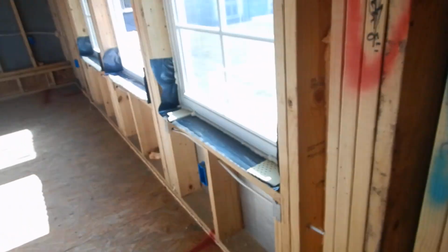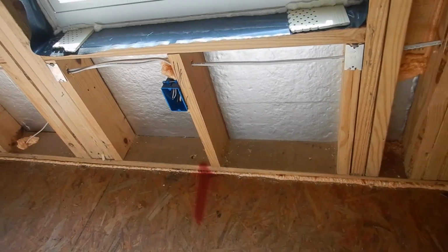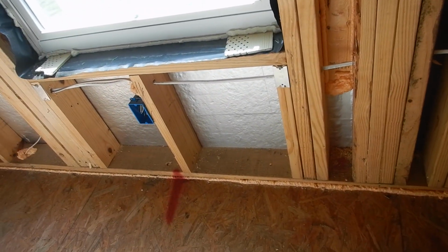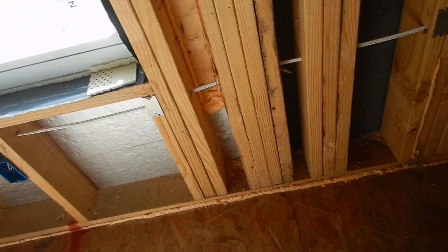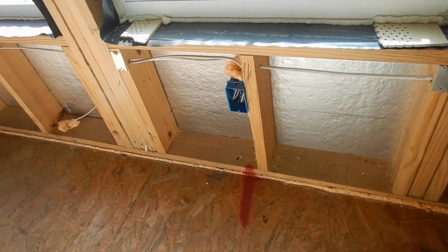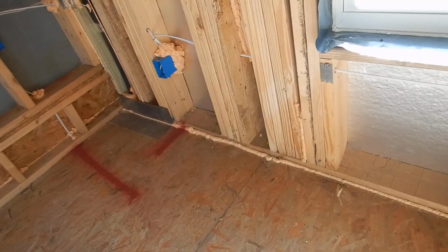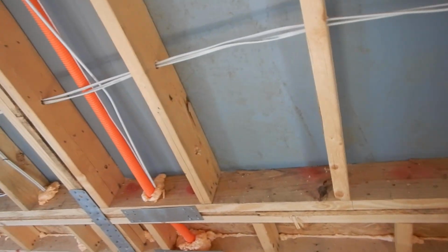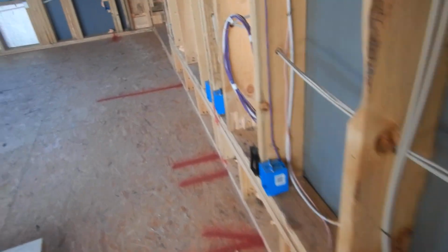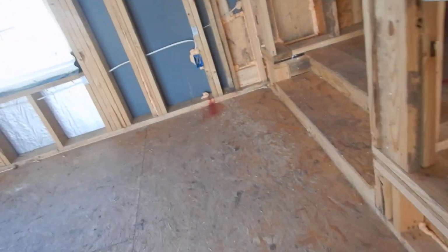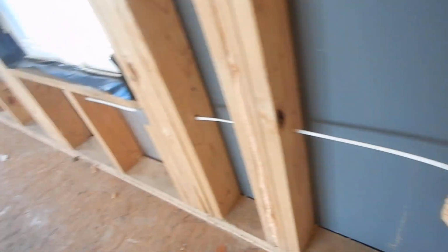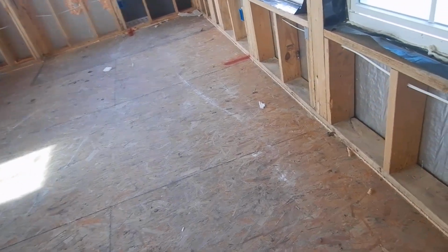Go over here. Hey, how about this? We're covering up the outlet box so that dirt doesn't get in there. Okay, I'm going to make a random sampling. These outlet boxes are supposed to stay clear. We've already got a couple videos about outlet boxes, and the cables and the loops going to them. I don't want to beat a dead horse. But when I come back, assuming that I'm invited back to inspect this house one more time, I'm going to open up a representative number of the outlet boxes, and I'm going to look for contaminants because we're not supposed to have contaminants in those boxes.